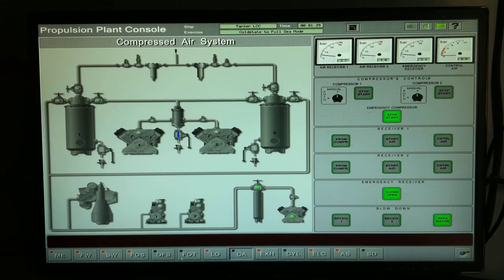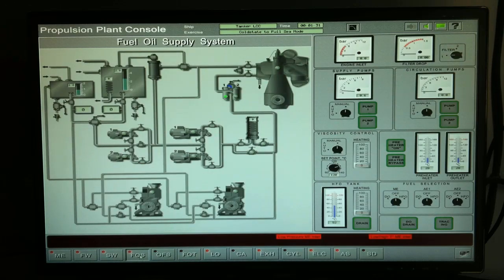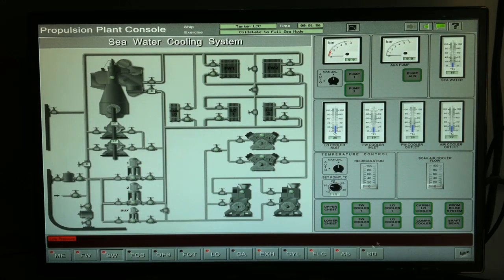Leave it running, then proceed to the fuel supply system. Fuel selection should be diesel oil. Then circulate the fuel system using the supply circulating pumps. So, preheater valve on, start supply and circulating pumps manually. Then seawater cooling system, open sea chest and open appropriate cooler valves.